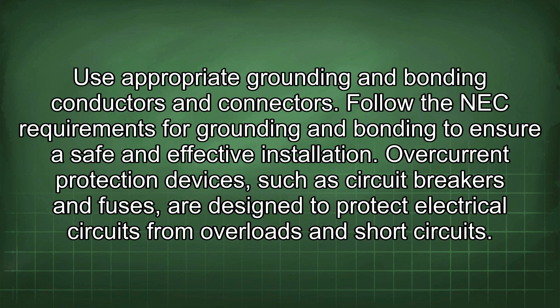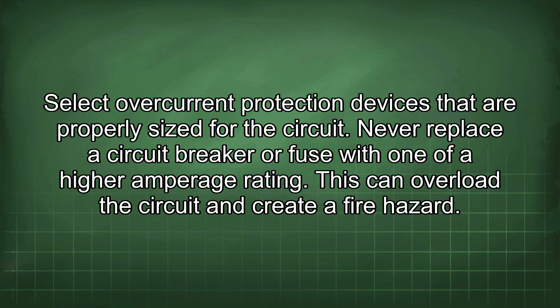Overcurrent protection devices, such as circuit breakers and fuses, are designed to protect electrical circuits from overloads and short circuits. Select overcurrent protection devices that are properly sized for the circuit. Never replace a circuit breaker or fuse with one of a higher amperage rating. This can overload the circuit and create a fire hazard.